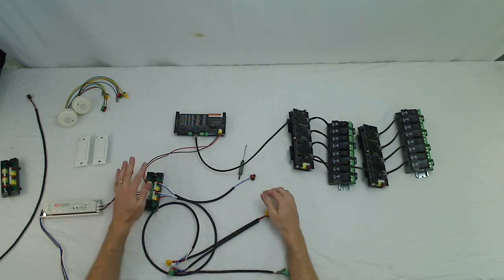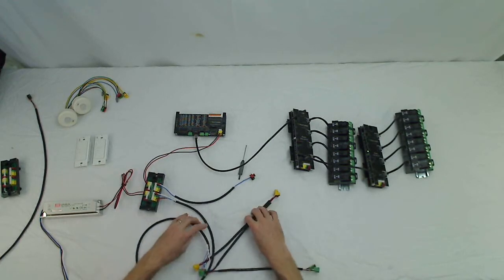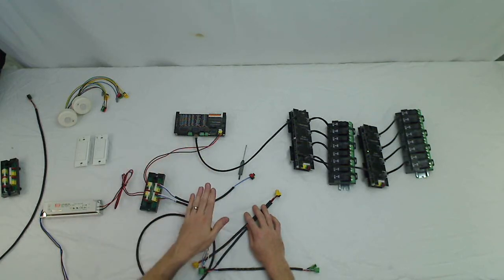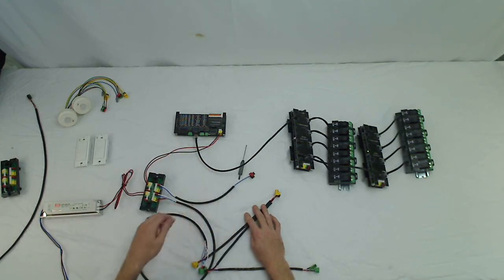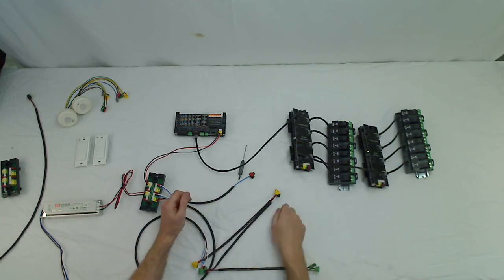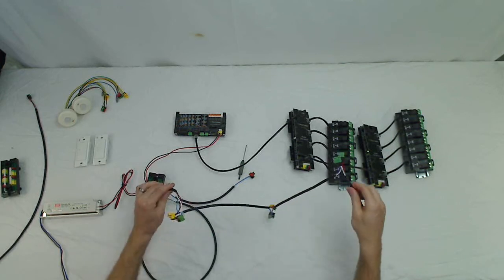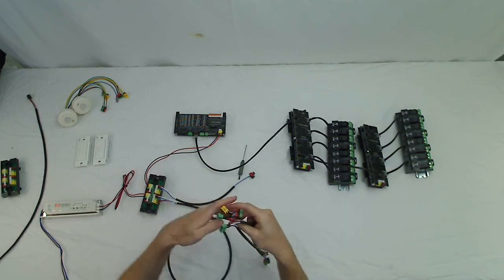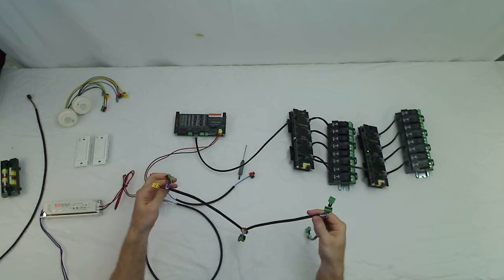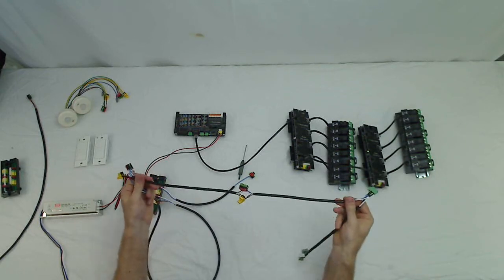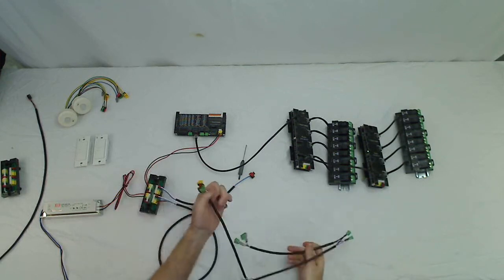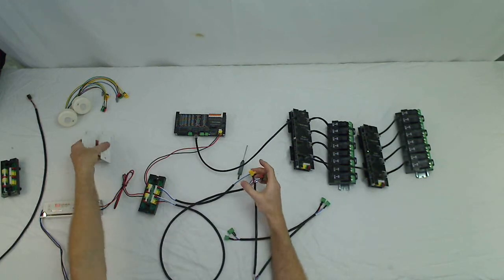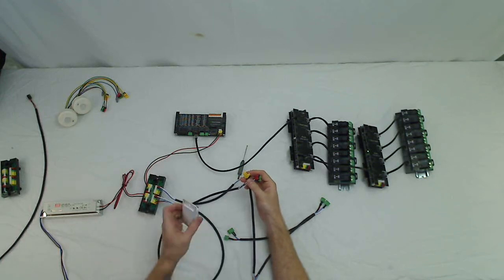And all of the five wire smart switch devices get wired in a daisy chain fashion. So essentially you start at the panel, you'll go to your first five wire station or sensor, and then from that daisy chain to your next station or sensor for your whole chain. So essentially what we've got here is we'll start at the controller panel, and we'll go to our first station or smart switch, and then on down the line. We've got four devices here.